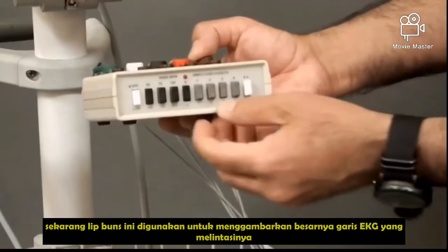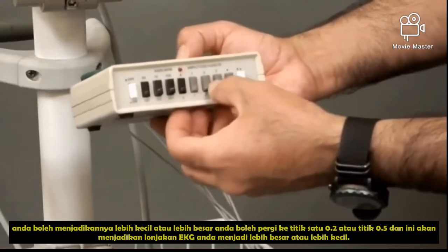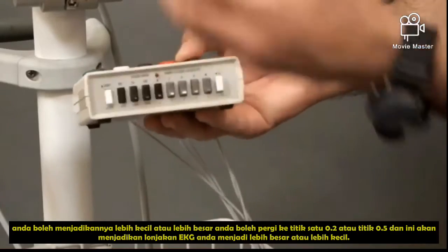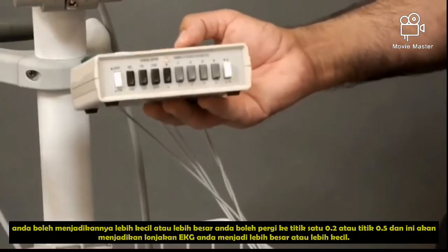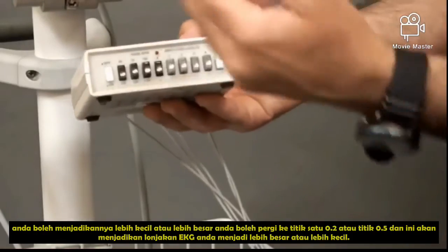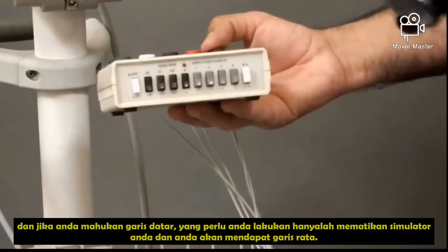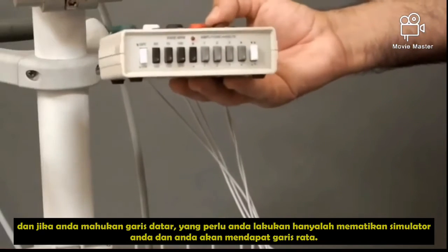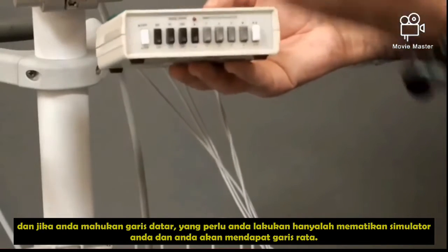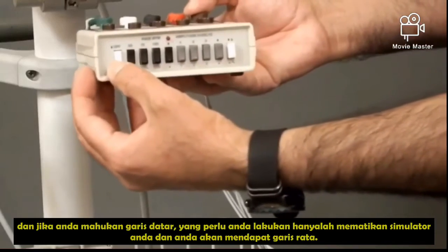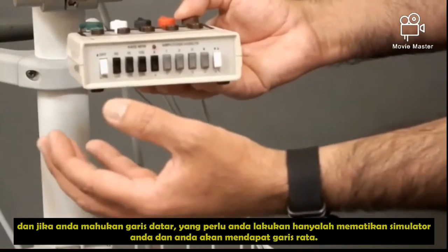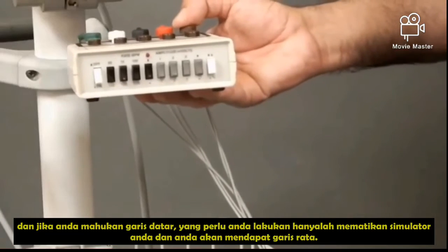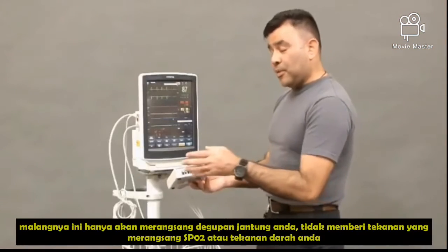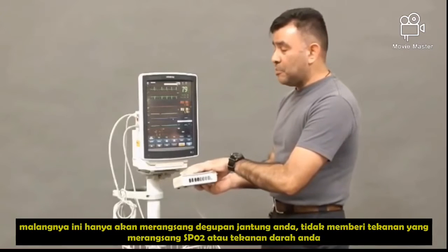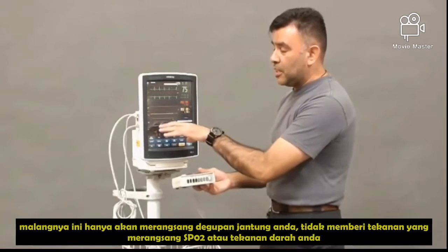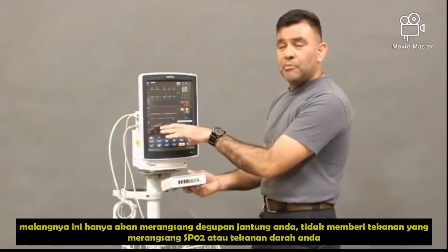You can make it smaller or bigger. You could go 0.1, a 0.2, or a 0.5. And this is going to make your EKG spike go bigger or smaller. And if you ever want to flat line the line, in case the script calls for the actor, the persona, to die, all you got to do is turn off your simulator and you're going to get a flat line going across. Unfortunately, this would only simulate your heartbeat. It will not simulate your SpO2 or your blood pressure.